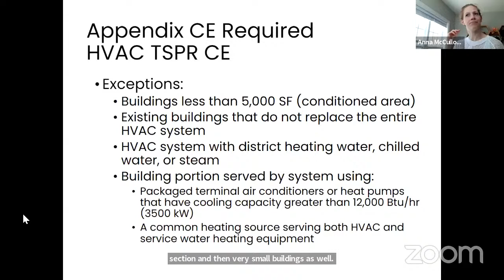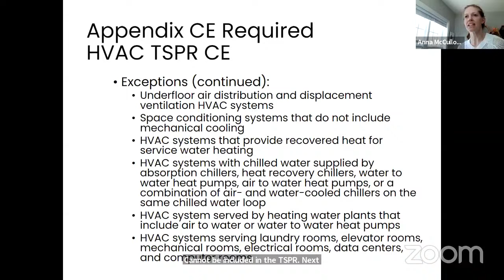Underfloor and displacement ventilation HVAC systems, HVAC systems with chilled water supplied by absorption chillers, heat recovery chillers, water-to-water heat pumps, air-to-water heat pumps, or a combination of air and water-cooled chillers on the same chilled water loop cannot comply with this section. HVAC systems served by heating water plants that include heat pumps, air to water or water to water heat pumps, cannot comply with this section. Laundry rooms, elevator rooms, mechanical rooms, electrical rooms, all of those HVAC systems cannot be included in the TSPR. Next slide. There's one more.